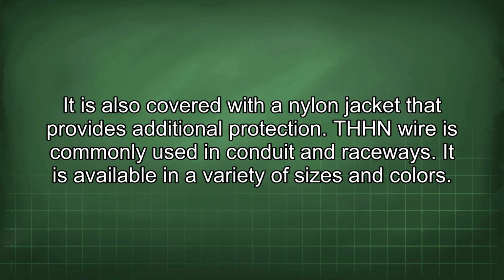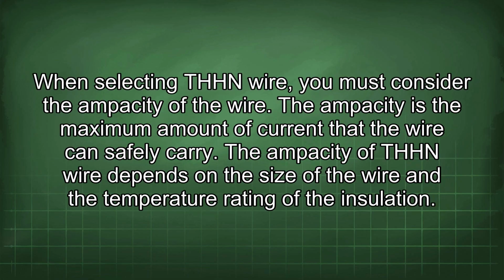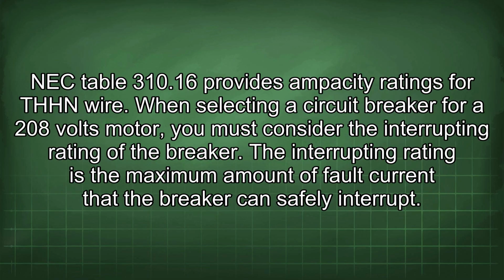THHN wire is commonly used in conduit and raceways. It is available in a variety of sizes and colors. When selecting THHN wire, you must consider the ampacity of the wire. The ampacity is the maximum amount of current that the wire can safely carry. The ampacity of THHN wire depends on the size of the wire and the temperature rating of the insulation. NEC Table 310.16 provides ampacity ratings for THHN wire.